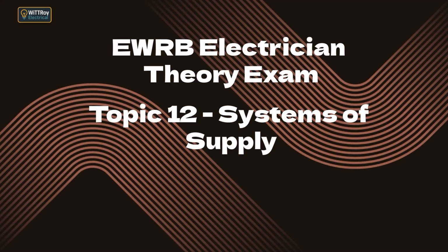12.2e. Explain that downstream distribution type systems may be connected to a MEN installation provided the same essential features are maintained. Downstream systems, such as generators or isolated supply sections, can be connected to a MEN installation as long as they maintain the same protective earthing principles. There must only be one MEN link, the earthing must be correct, and the fault path must allow protective devices to disconnect quickly. As long as these conditions are met, downstream systems remain safe and compliant.